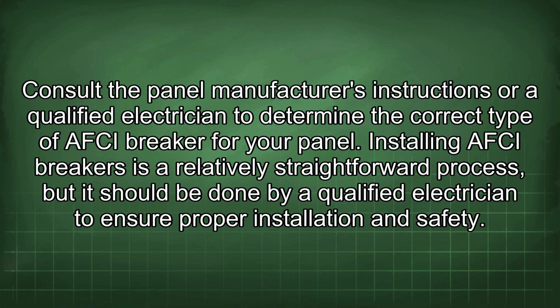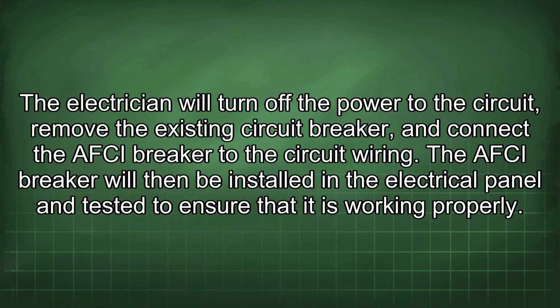Installing AFCI breakers is a relatively straightforward process, but it should be done by a qualified electrician to ensure proper installation and safety. The electrician will turn off the power to the circuit, remove the existing circuit breaker, and connect the AFCI breaker to the circuit wiring. The AFCI breaker will then be installed in the electrical panel and tested to ensure that it is working properly.